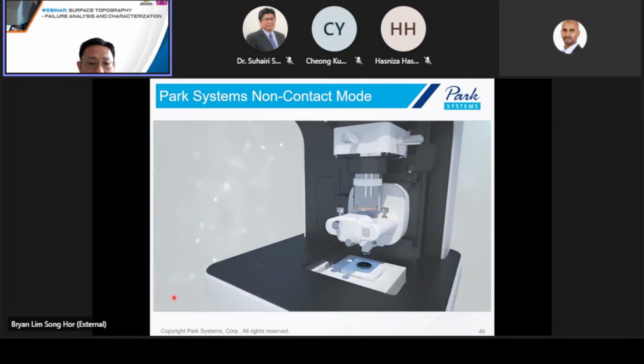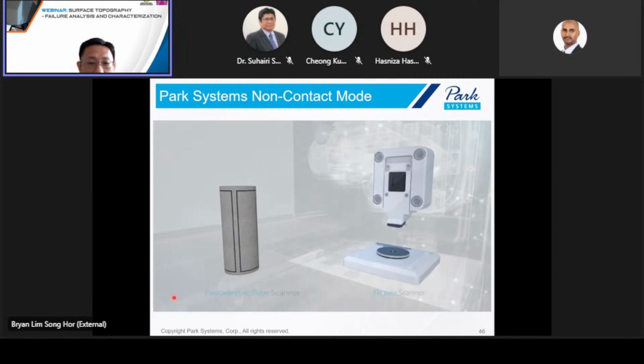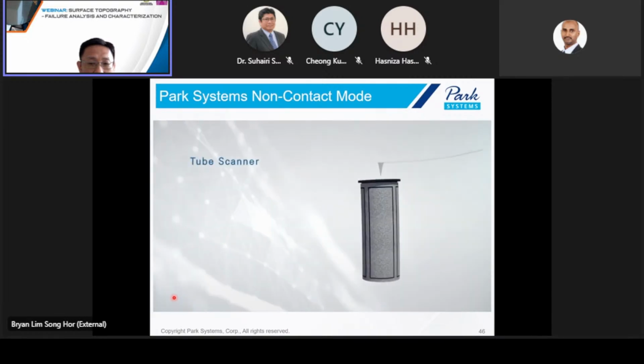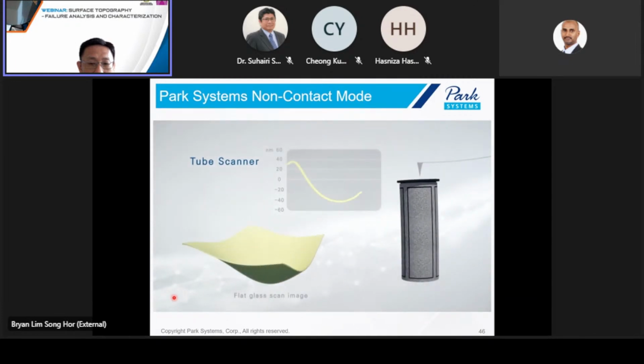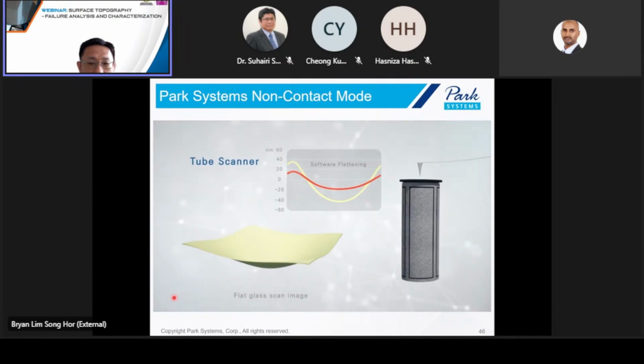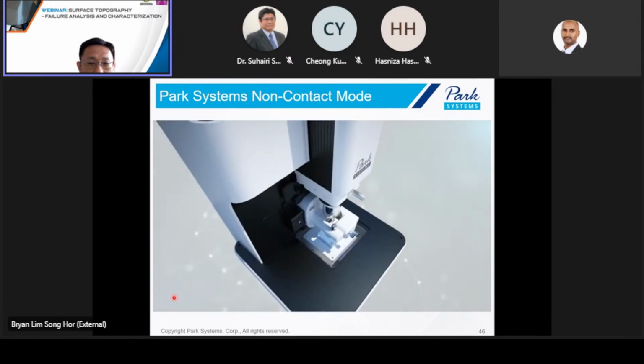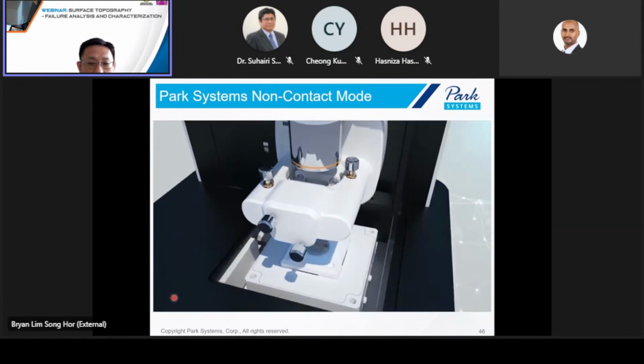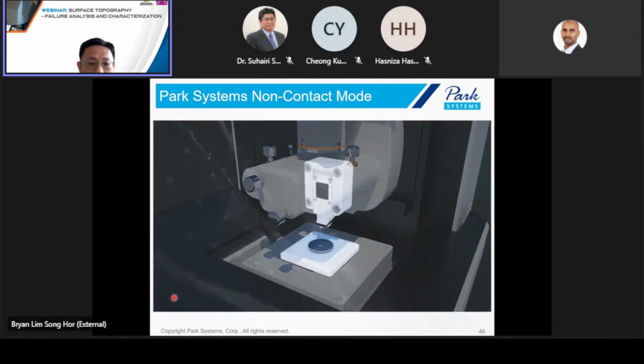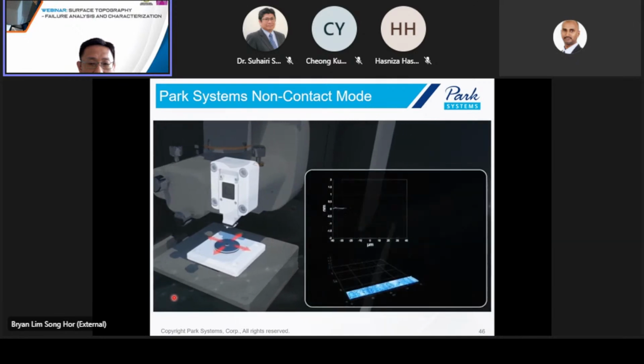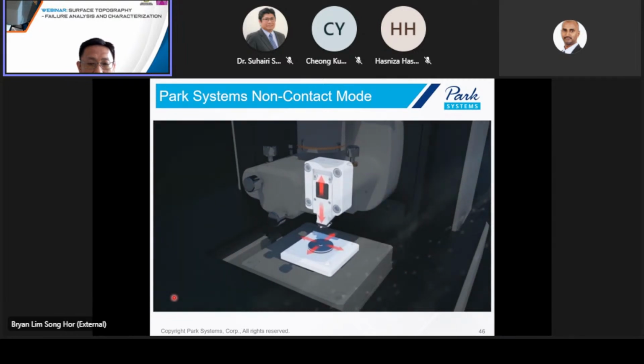The fundamental technological difference between Park Systems and other companies is in the structure of the scanner, which is the core of an atomic force microscope. The old atomic force microscope design used a tube scanner, which relies on the tube's curvature to alter the relative positions of the probing tip and sample. But this method creates image distortion as the tube curves to the side and warps XYZ measurements. In contrast, the decoupled scanner design developed by Park Systems consists of flexure-based independent X, Y, and Z scanners, so that measured images can be free of distortion and excellent in linearity and orthogonality regardless of scanning range or sample size, and at any scan location or speed.